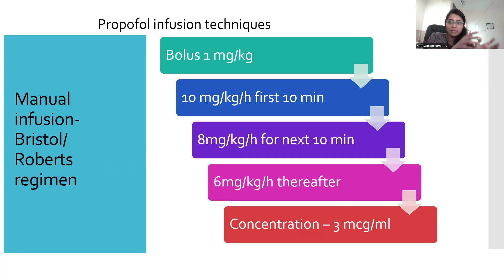Suppose the patient is somewhere around 60 kgs, you give 60 milligrams as bolus, followed by 10 into 60, that is 600 milligrams per hour for the first 10 minutes, then 60 into 8, 480 milligrams per hour for the next 10 minutes, and then 360 milligrams per hour thereafter. That is how you do it. So you set the infusion pump. 360 milligrams means you should set 36 ml per hour. That is how you set the whole infusion pump.